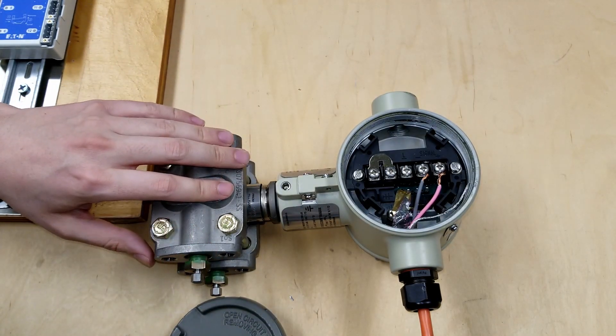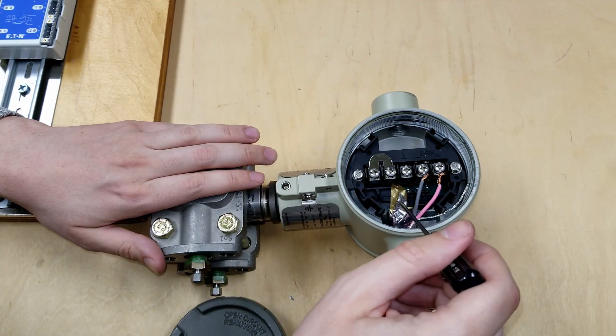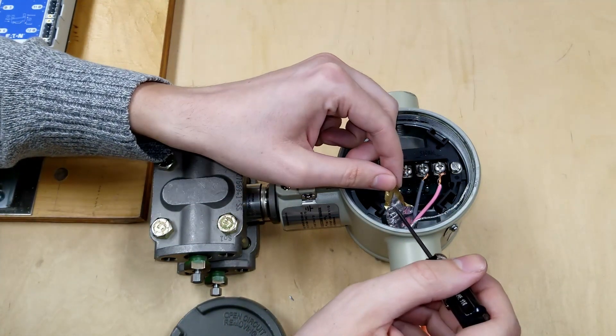One area that's often overlooked is the inside of the instrument case. Here you can see that the shield drain wire is touching the outside of the case, causing an intermittent ground. The same could happen with the foil.